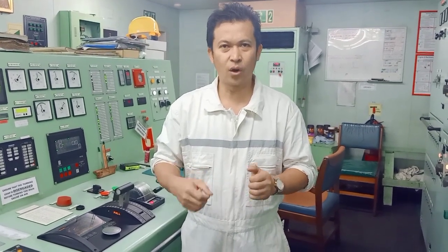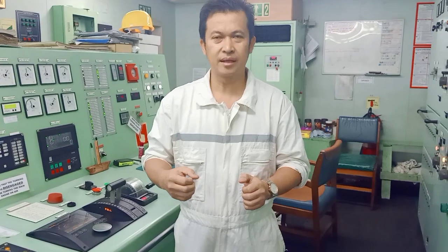We had encountered a trip-off from a circuit breaker, ballast number 2, that went burnout due to very strong current. Ballast number 2 is used for trimming and stability of the vessel. Now I'm going to show the procedure on how to replace a circuit breaker in a live circuit bus bar.